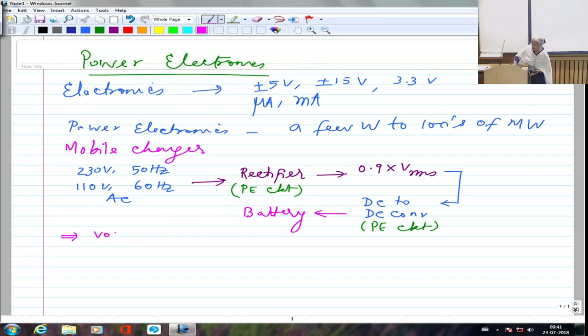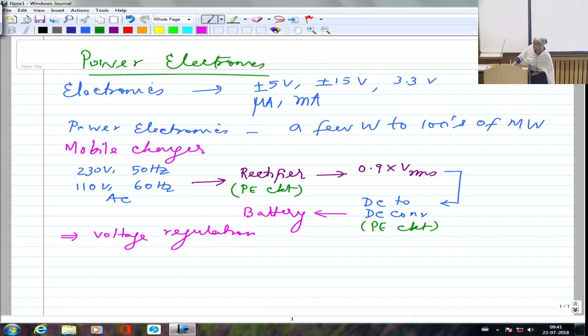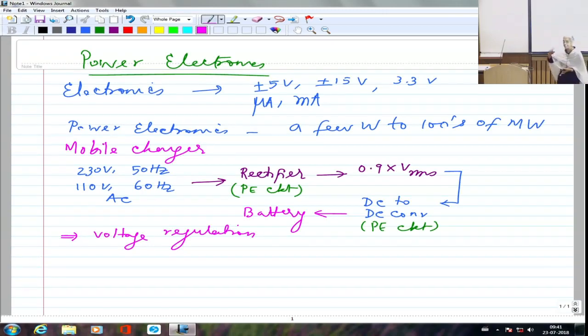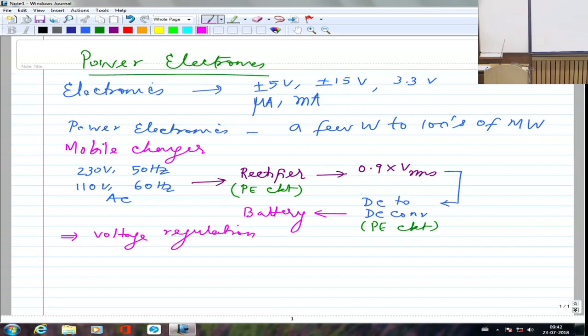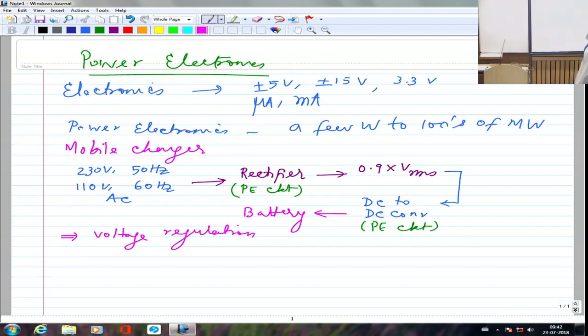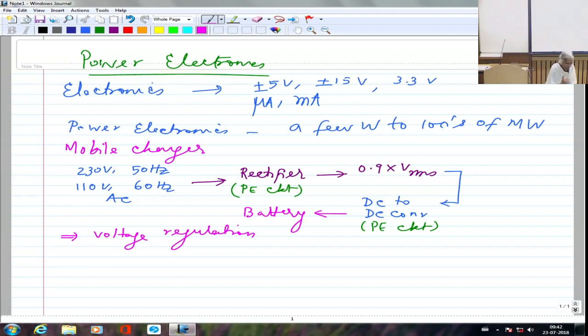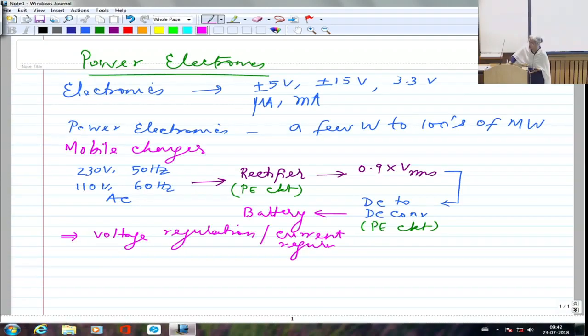The output is regulated to the battery. If the grid voltage drops from 230 to 180 volts, the charger should still supply the same voltage to the battery. So voltage regulation must be done. The battery voltage itself varies — a 5-volt battery can reach 5.5 V when fully charged and drop to 4 V when discharged. Despite those variations, both the current going into the battery and the voltage must be regulated.